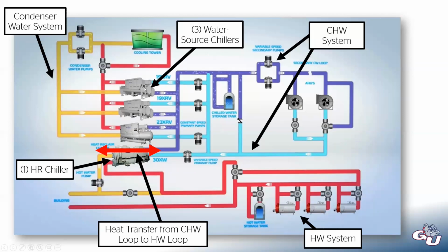And this is fairly common to have essentially a mix and match. It's not all heat recovery chillers. Usually you still have the water source chillers that are serving most of the load, and then you might have 1 or 2 heat recovery chillers to take advantage of that. But it kind of depends on how much of that heat recovery benefit we can actually see. It might be overkill to have 4 heat recovery chillers here.